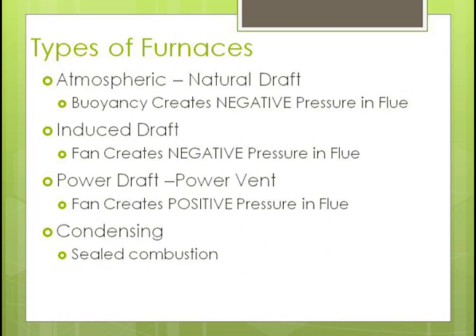An 80% furnace can't be sealed up because it needs air from the room for combustion. It needs room air to provide a carrier for the draft going up the flue. Old furnaces work the same way with the little cap that sends gases up. When you go to an 80% furnace with induced draft, they seal that up and put a fan in to carry the bad gas away. If it's induced draft, it creates negative pressure in the flue; power draft creates positive pressure in the flue.